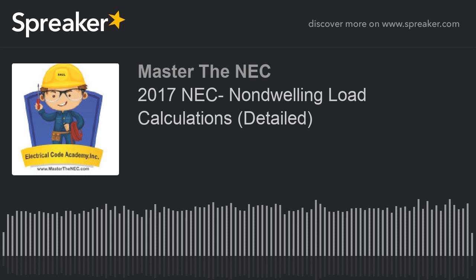All right, so now at that point, we have done our receptacle calculations, all right? And now we're moving into the general lighting loads. Now, general lighting differs from what we did in a residential because the general use receptacles were wrapped up inside of the general lighting by 220.14(J) when we're doing a dwelling unit.